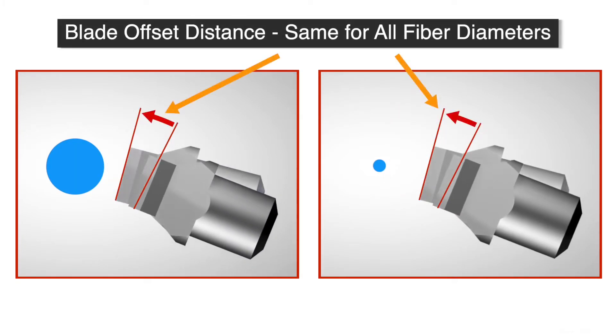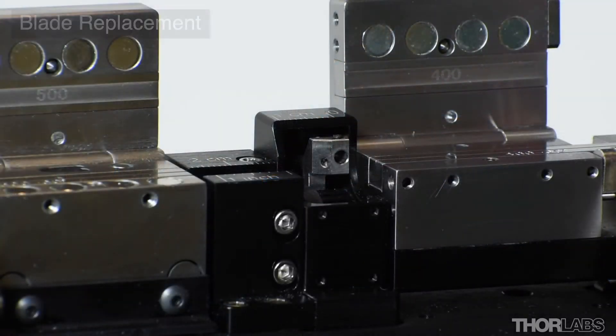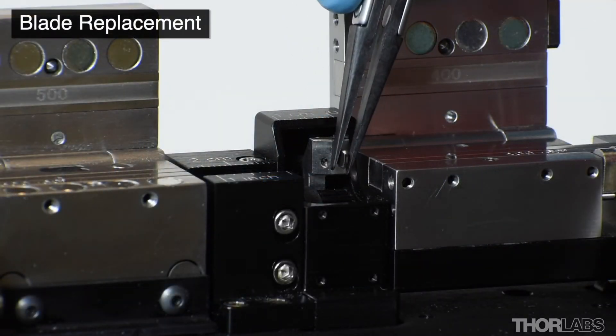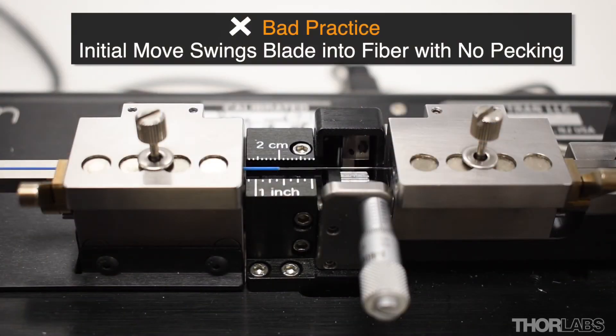As the blade offset applies to all cleave files and fiber sizes, it only needs to be modified when a blade is repositioned or replaced. This accounts for variation in the blade dimensions and the position of the blade. This will prevent the blade moving too far forwards into the fiber and being damaged prematurely.